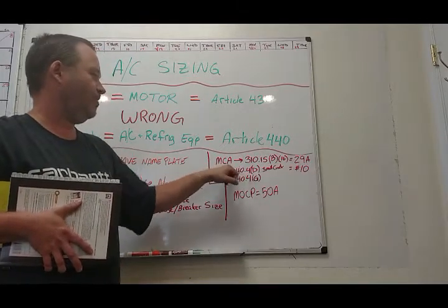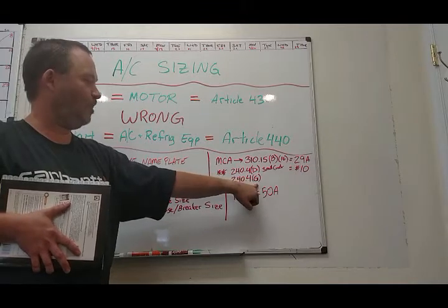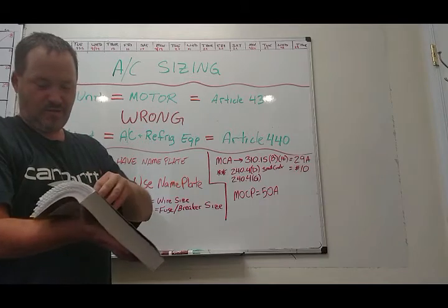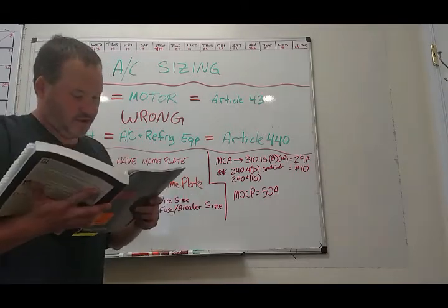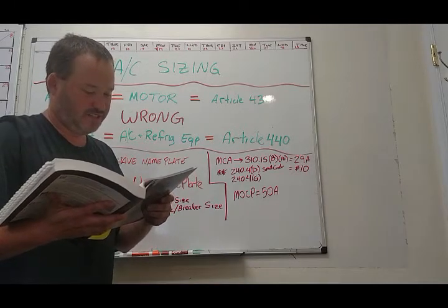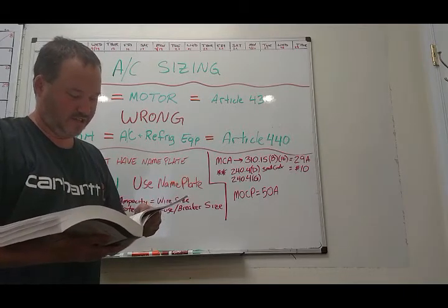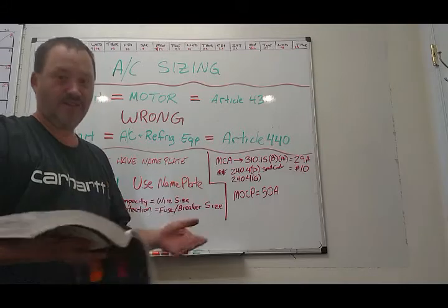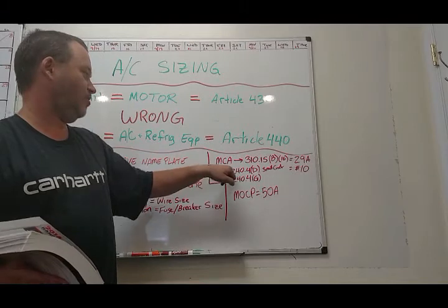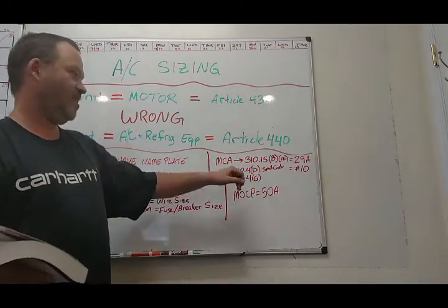But if you continue to read 240.4, you get down to 240.4(G). 240.4(G) says that overcurrent protection for specified conductors shall be permitted to be provided as referenced in Table 240.4(G). The very first item listed is air conditioning and refrigeration equipment circuit conductors. So right there it tells you in 240.4(G) that the double asterisk in the table up here does not apply there. You can use alternate calculations.